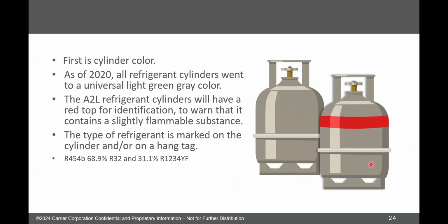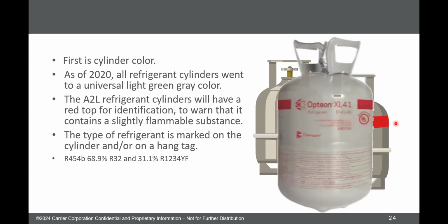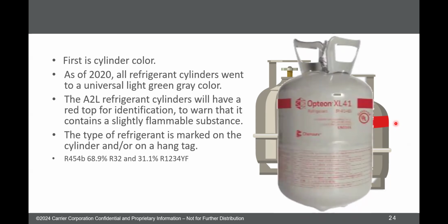A2Ls are also going to be gray and boring. The difference is they're going to have a red band painted on to let you know they're an A2L. So this jug right here for R454B looks exactly the same as a jug for R32, and you'll have to actually read what it says on there to know which one you have, because visually, it in fact will look the same. But in any case, they're all gray.